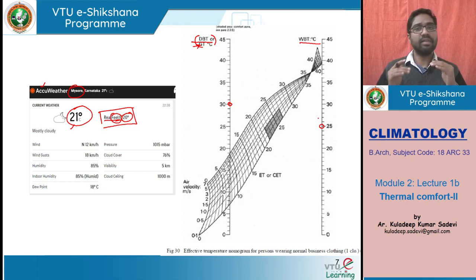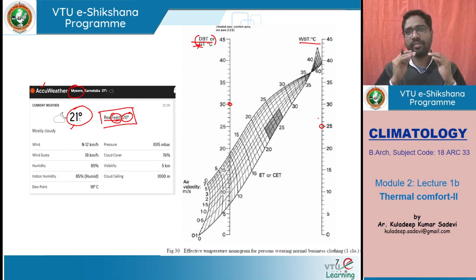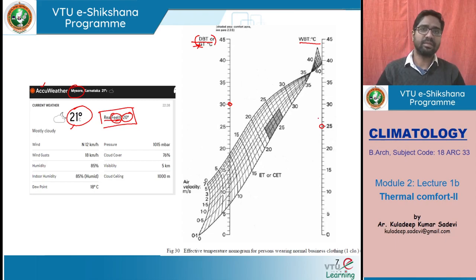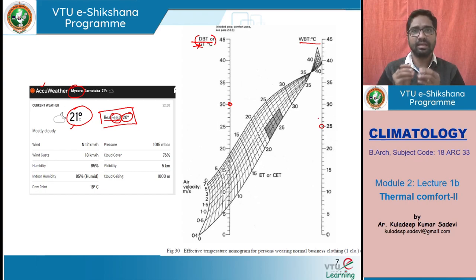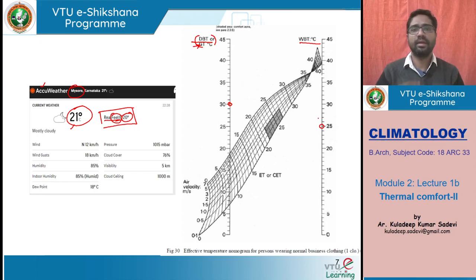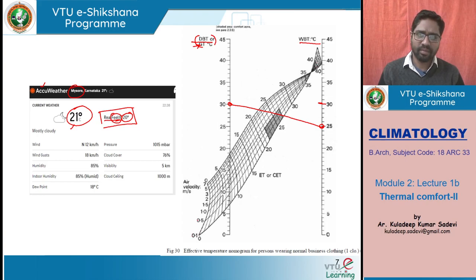We should understand that wet bulb temperature is always equal to or less than dry bulb temperature — wet bulb temperature cannot be more than dry bulb temperature. Wet bulb has a wet cloth which keeps evaporating moisture, and if the surrounding air is comparably drier, that makes the thermometer reading cooler than the actual temperature. So if the dry bulb temperature is 30 degrees centigrade and wet bulb temperature is 25 degrees centigrade, if we draw a line between dry bulb and wet bulb on the chart, and there are different velocity lines — 0.1, 0.5, 1 meter per second — at 1 meter per second air velocity, the line meets at around 26 degrees centigrade effective temperature.